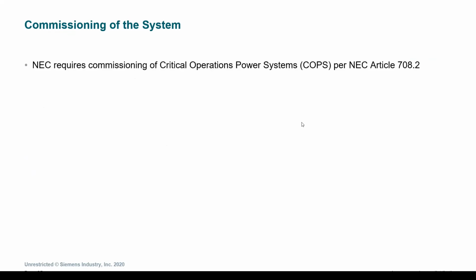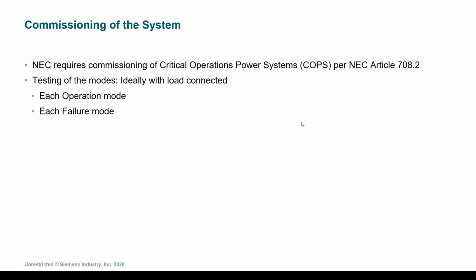As a construction project comes to a close, the commissioning of the system is very important. First of all, I just wanted to address that it is required by the Critical Operations Power Systems per NEC 708.2. And before the system is even shipped, the paralleling switchgear is factory pre-programmed, and this has a lot of everything ready before the commissioning agents and the service technicians are on site to commission the system. As part of the commissioning process, the training of the facilities team to go through each of these functions, they will be involved in this as well.